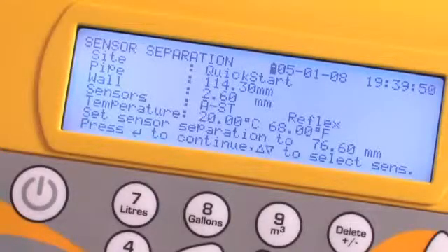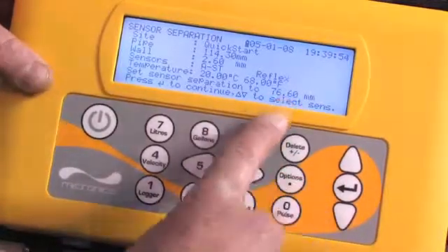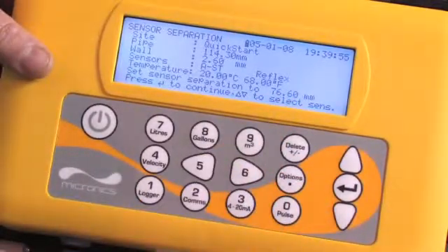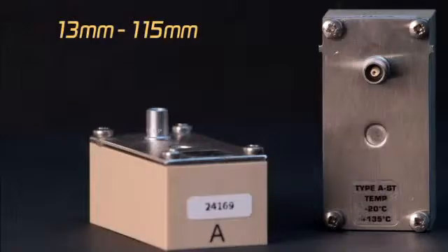the unit calculates which sensors to use and the separation distance to set them on the pipe, in this case to 76 millimeters, ensuring that the right type of sensor is selected. In this case, A standard for the standard sensors, for pipe sizes 13 to 115 millimeters.